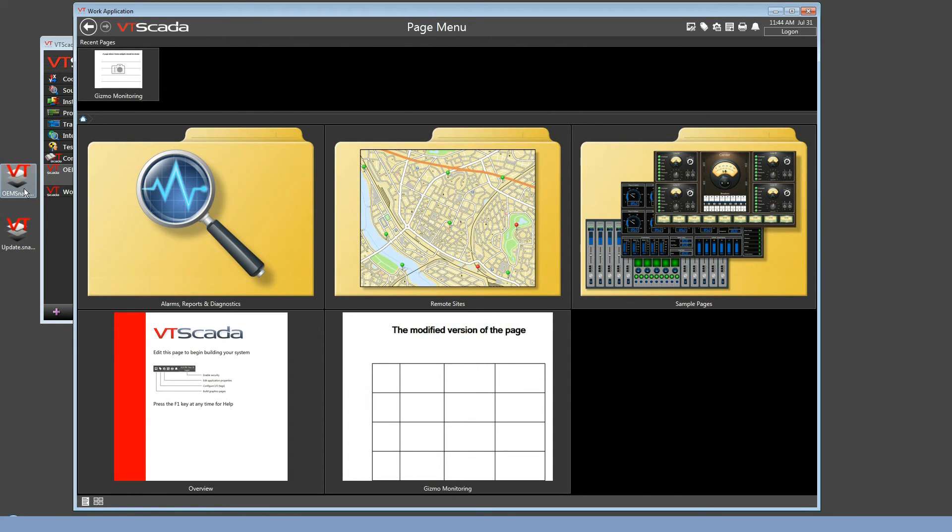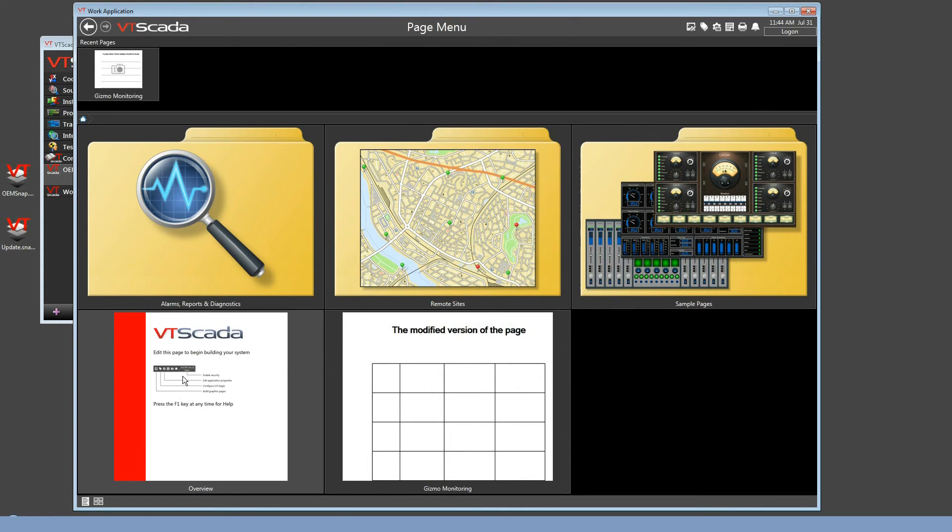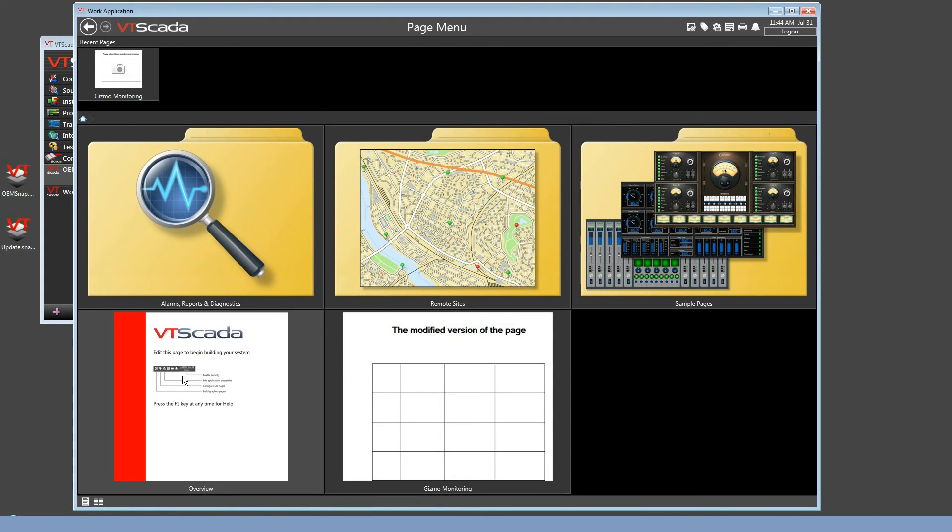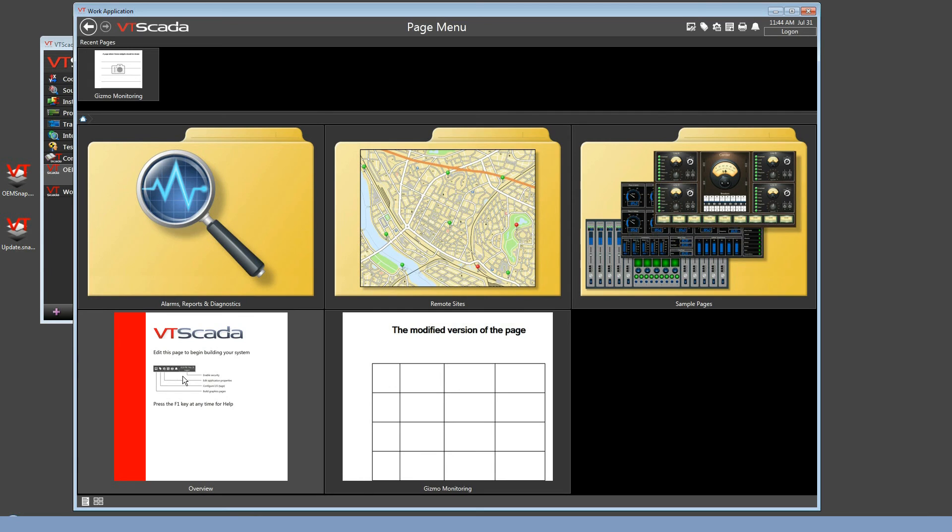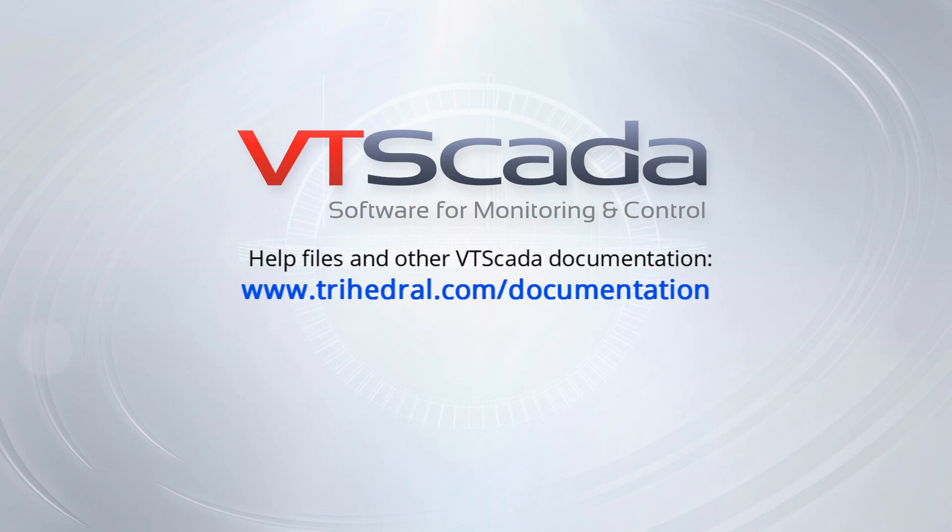Otherwise, before creating the snapshot from the OEM layer, what you should do is, in the OEM layer, delete your local copy of the Overview page. And remember, you're only deleting that layer's local copy or override of the base Overview page, which comes from the VT SCADA layer. So, if you get rid of it in your OEM layer, then the VT SCADA layer's version will then again be available for all the descendant applications. Note that after you delete it, though, you'll probably have to recreate the menu link to that Overview page. For more information about the finer details of working with layers, please refer to the VT SCADA's online help files.